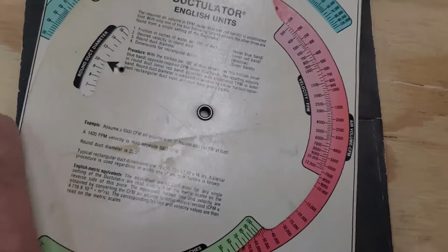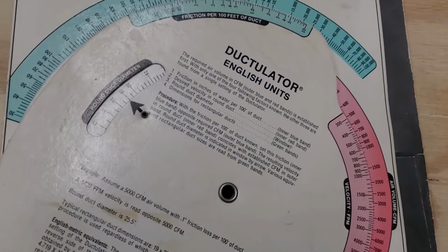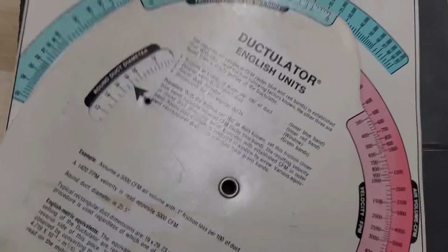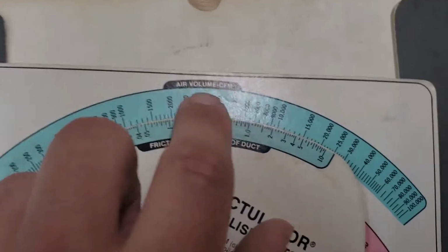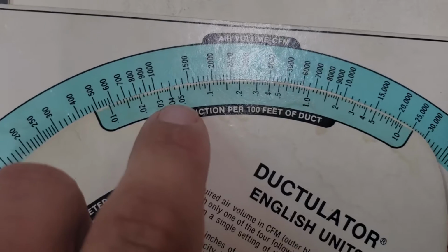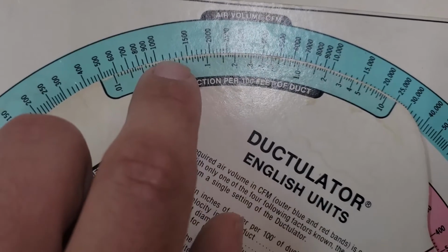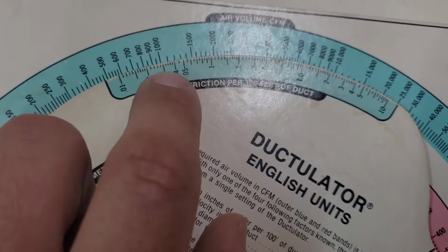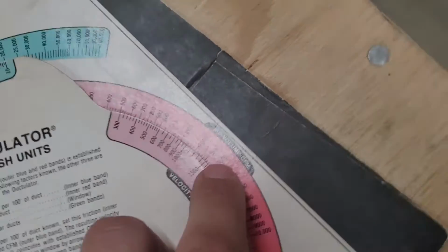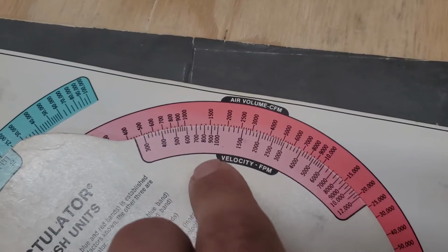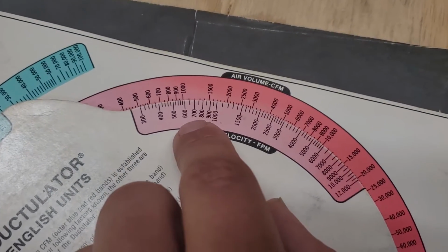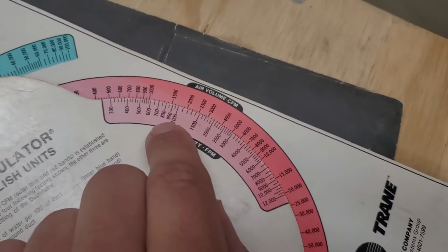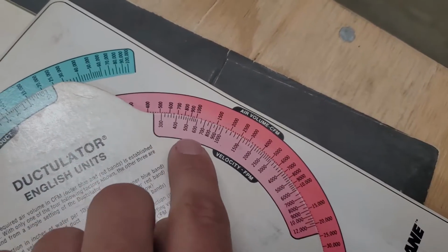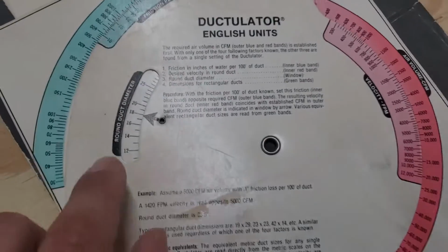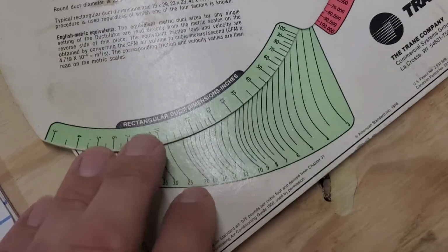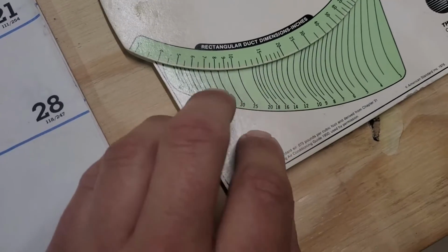Really quick, let's just read through this so I can show you a bit. All right, let's scroll to 18-inch round duct, okay? Coming up here to see the CFM that correlates to 0.05 static, looks like we're in between 13 and 14, let's just say 1300 CFM is what we got. Come over here to CFM, go to 1300, and looks like we've got about 750 feet per minute. So at 1300 we're going to have 750 feet per minute coming out of that duct, okay? And that's 18-inch round. Now what is the rectangular duct equivalent? We've got several choices here.